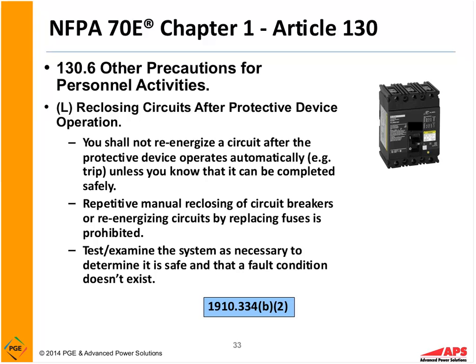And if you look at the UL listing on a lot of the breakers, a lot of times they're only tested at UL to trip 2 times at their fault current rating. Okay, so in other words, if it's tripped twice at its full fault current rating, then the breaker should be replaced.